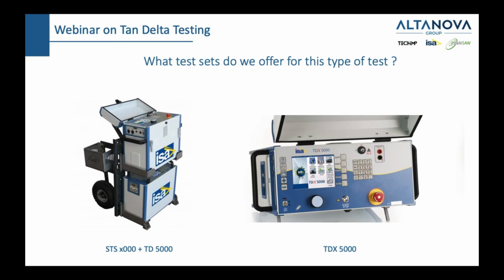Is ISA building a library of test values for various transformer models and bushing models to offer as a test guide? Well, we didn't do that because in the last 7 years we were mostly guided by the 1% value. For a bigger transformer, what usually happens is that the asset managers have the initial values, and we compare with the initial values. That's what helps us understand what is actually expected from us. But I'm not saying that it will not happen in the future. So let's continue if we want to do all the steps.